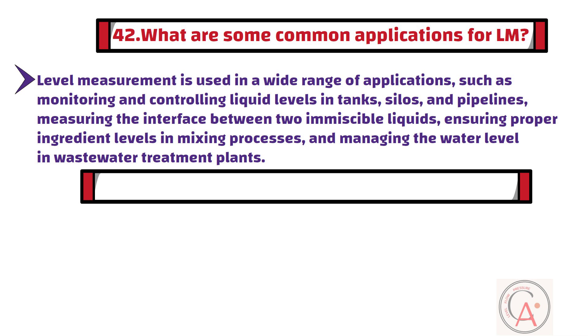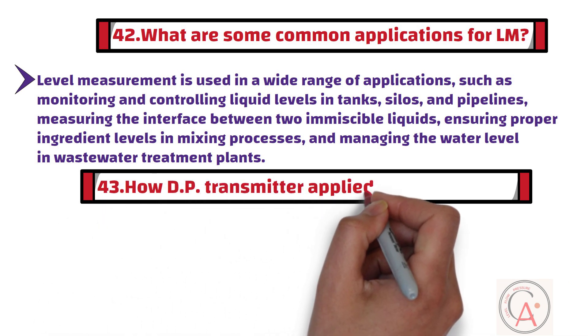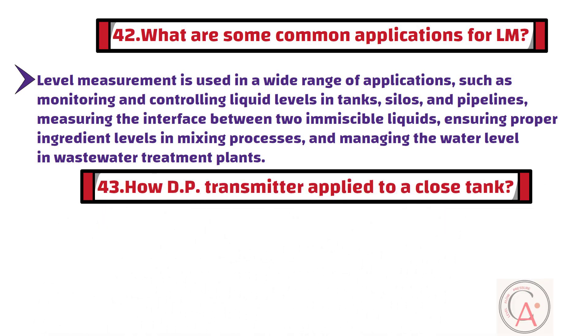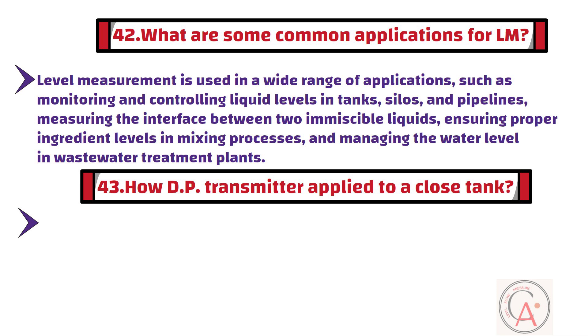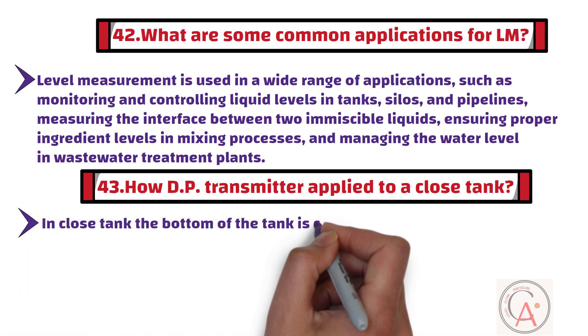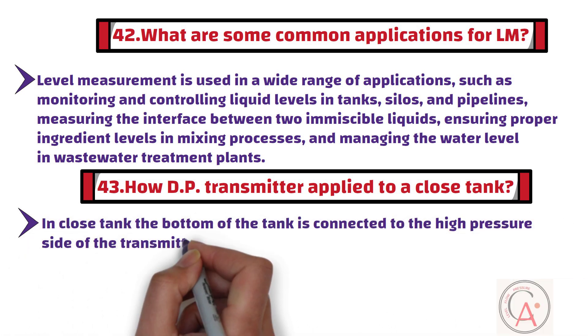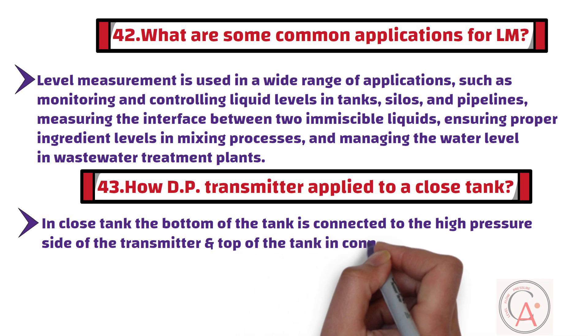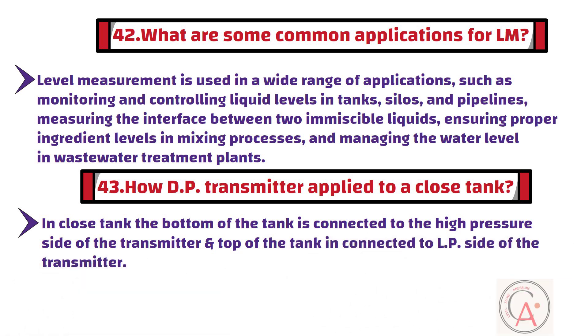Question 43: How is the DP transmitter applied to a closed tank? In a closed tank, the bottom of the tank is connected to the high-pressure side of the transmitter, and the top of the tank is connected to the LP side of the transmitter. In this way, the vessel pressure is balanced.